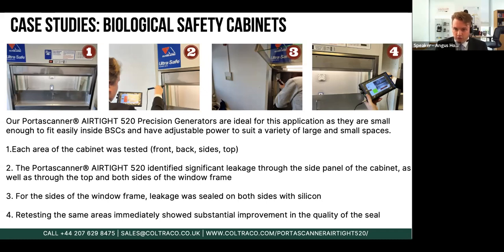However, this can introduce contaminants into the filter or just into the cabinet itself. So we brought along a Portascanner and we tested the cabinet that you can see on the images here. We tested a few areas of it, the front, the back, the sides, and the top, including a couple of areas that the manufacturer expected to find some leaks. And we absolutely did very quickly. We found leaks in all of these locations. This cabinet was one that had not had final sealing yet, so this was expected.